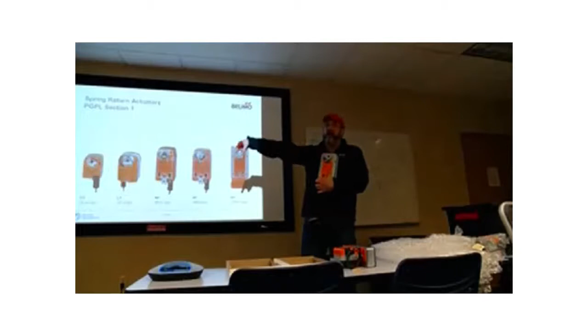It has to do with the 0 or minimum position of the drive signal. For instance, if the arrow is pointing this way, it tells you the minimum position of the control signal is all the way clockwise. And this switch means it's all the way counterclockwise. That sets the normal position of the damper. Which side you have facing you determines the fail rotation of the damper system. So we've got normal, we've got fail - 2 different things entirely.